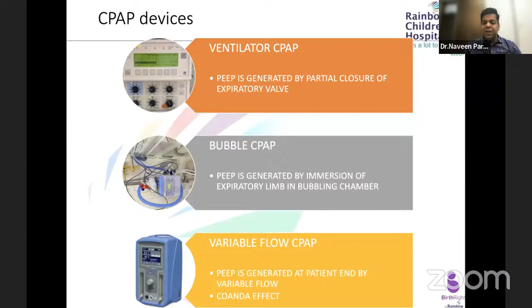And in variable flow CPAP, these are the flow drivers. I'm not going to talk much about it. In 2000 or 2005, they were the new kid on the block and they were very favored. But then the data came and it was found that bubble CPAP is equivalent to variable flow CPAP, and variable flow CPAP, being expensive, has now become out of favor in neonatology. Especially in our country, we feel that bubble CPAP is a very good thing. In variable flow CPAP, the infant flow driver, there is a Coanda effect by which the work of breathing is less. Okay, anyhow, coming to bubble CPAP, a simple and inexpensive thing.